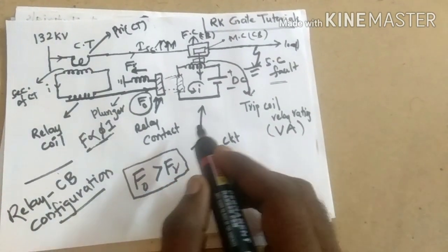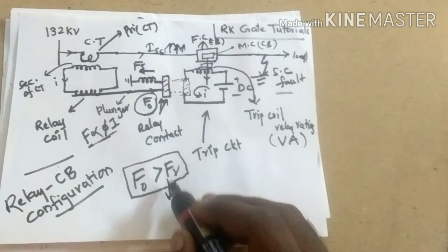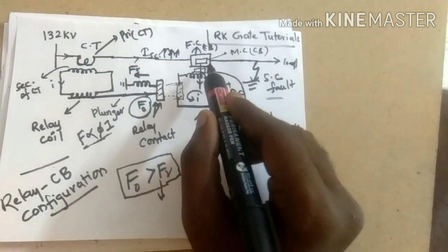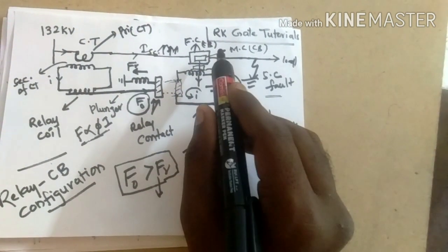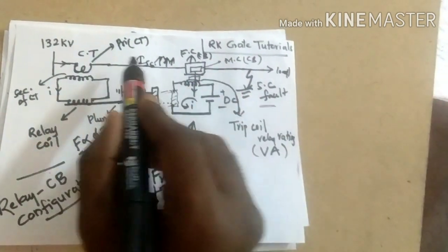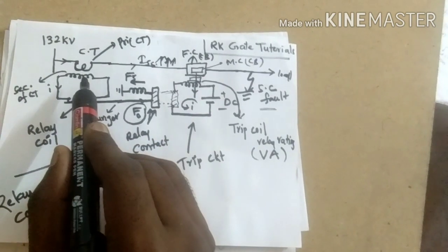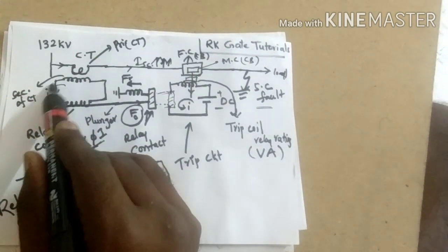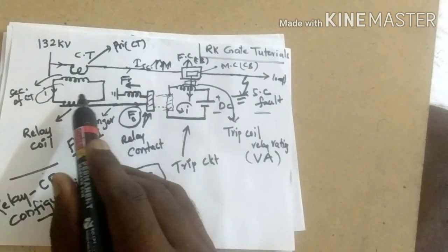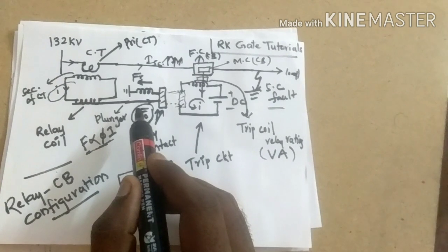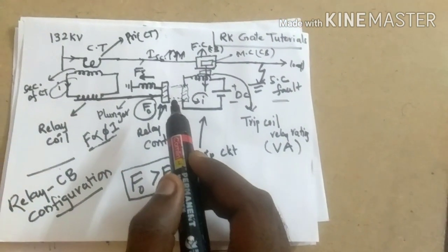This is the relay and circuit breaker configuration. The condition to operate the relay is: operating force greater than the restraining force. When the operating force exceeds the restraining force, the plunger moves — the relay contacts close the trip circuit — current flows in the trip coil, the trip coil pulls down the moving contact of the circuit breaker, which opens the line. This operating force is generated by the short circuit current, which causes excess current in the CT secondary, producing more flux, which generates the operating force that moves the relay contact forward.